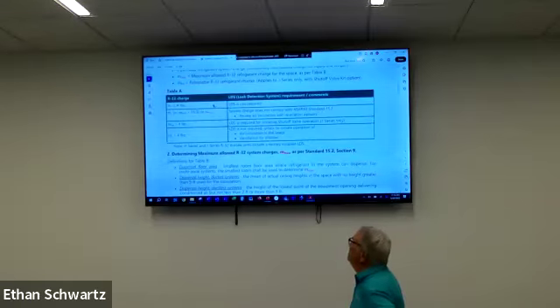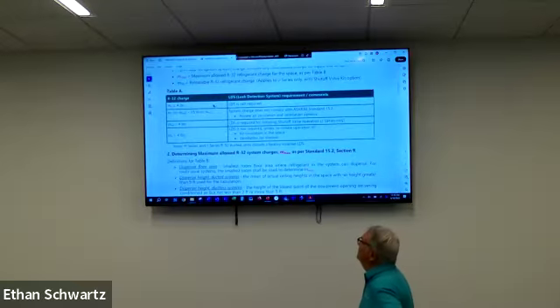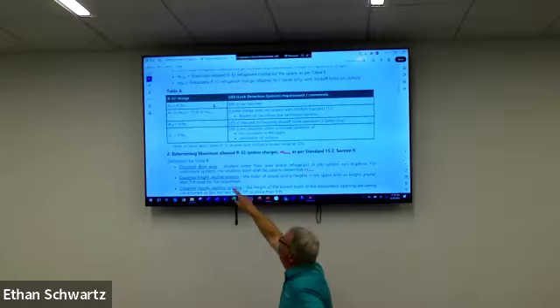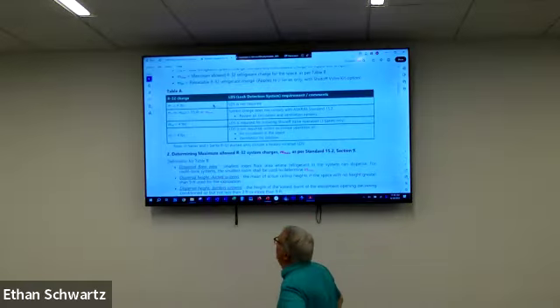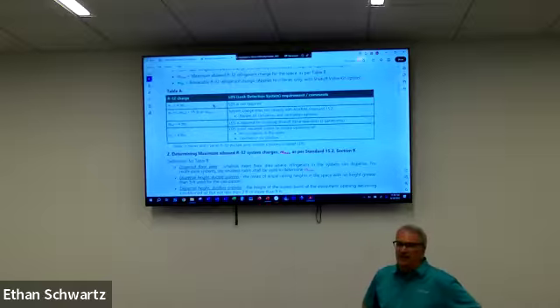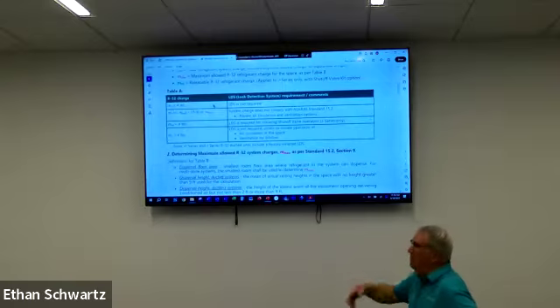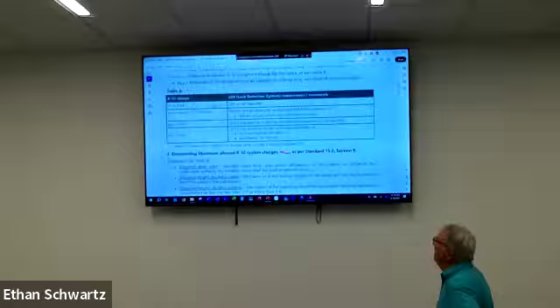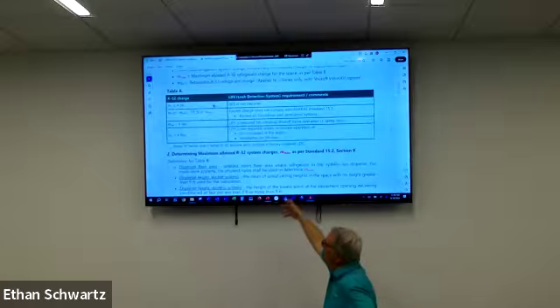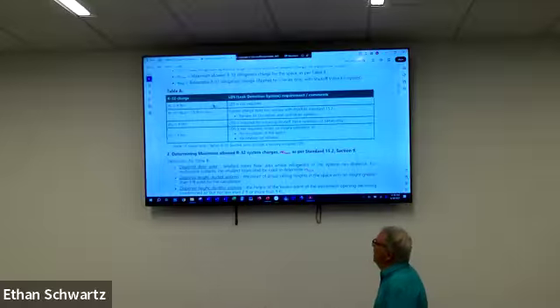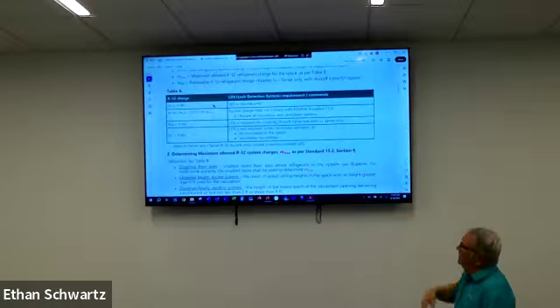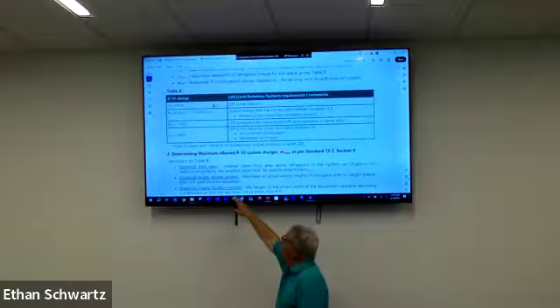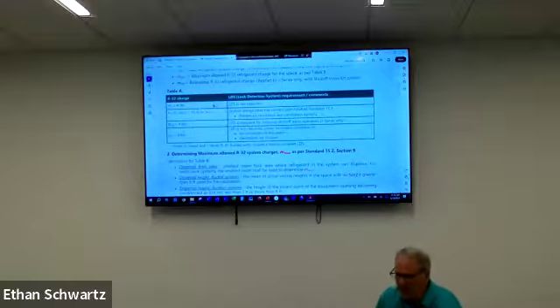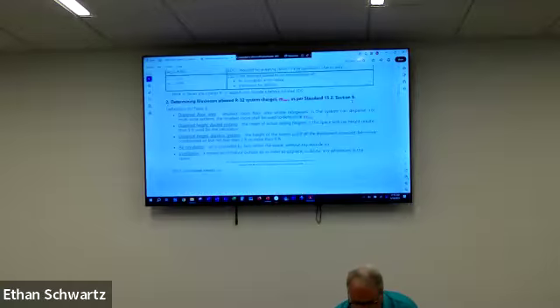It's when you get above 4 pounds that you start to get into a leak detection system and/or an RDS, a refrigerant detection sensor. So you can see here that MREL, that is the maximum releasable amount of refrigerant, referencing back to those shutoff valve kits that we have. And then we have to know the size things on here. What's the area of the room? We have to know the height of the room, and if it's a ducted system. And then if it's a ductless system, we have to know what's the bounding height of that indoor unit. And so this boils all of that down.